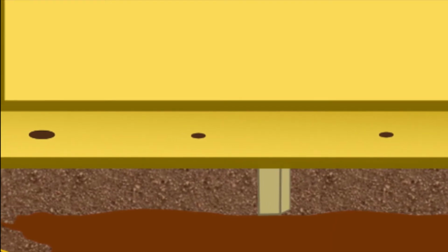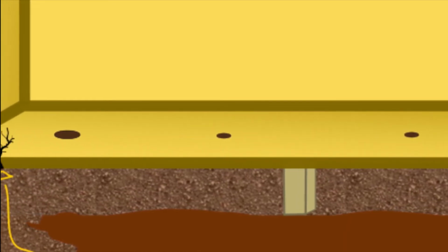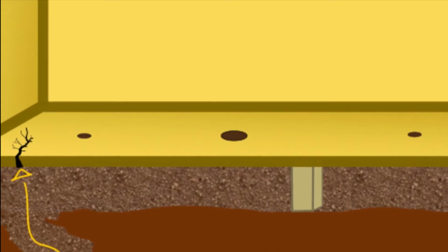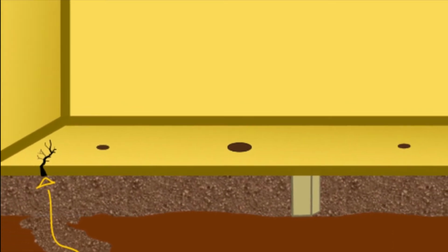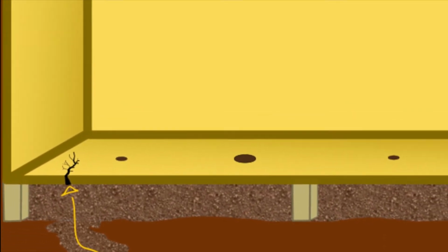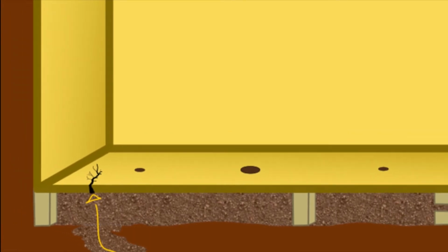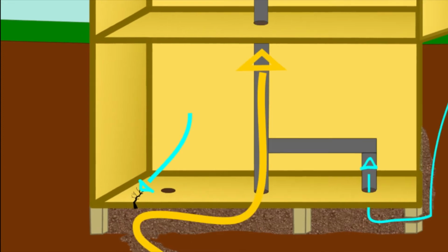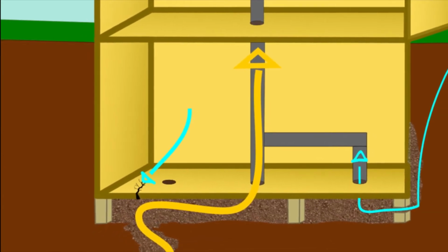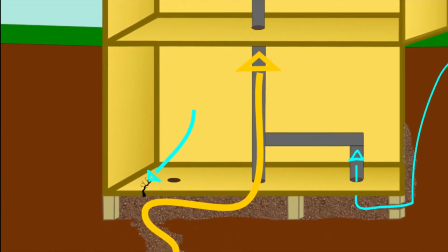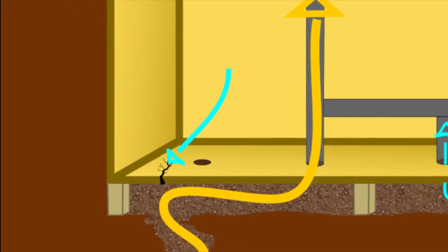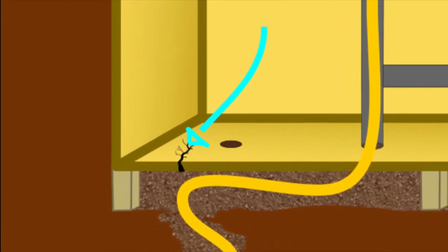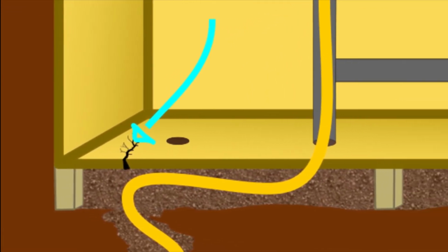In this example, it's a strip footing, but a blockage could be caused by many things. So, the mitigator would then put the shop vac on the middle hole in hope that it would communicate with the other holes, but in this case, we're still not communicating with the hole on the right. To resolve this, the mitigator would run a jumper to a part of the slab where there was no communication. The theory is that radon is diverted from the crack and is exhausted.